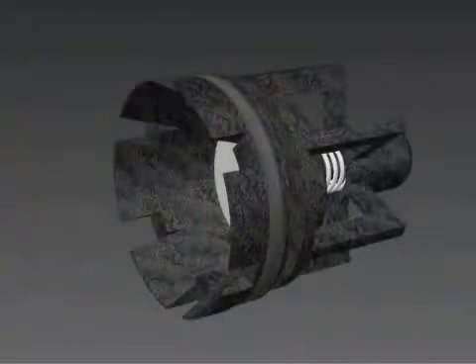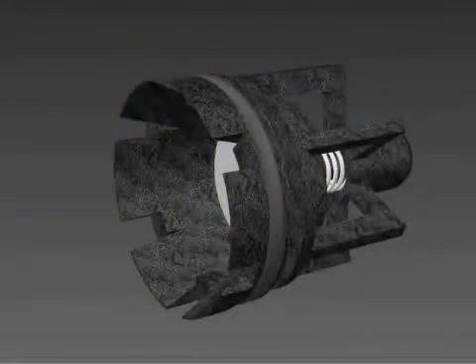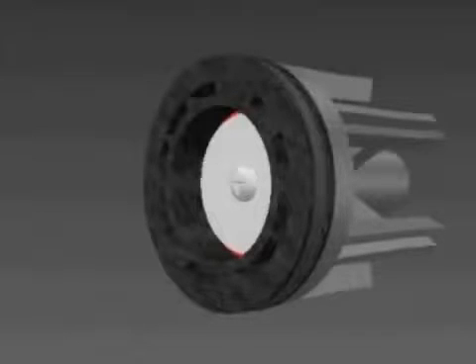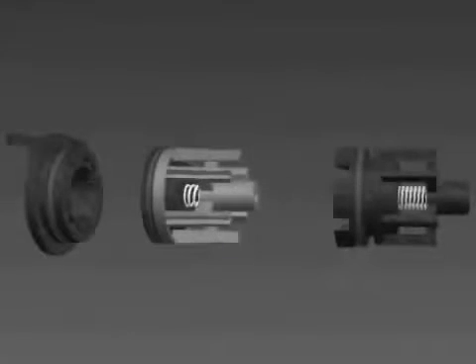Repeat this process with the second check assembly. Make sure to put the stronger spring in the number 1 check assembly. Now you will place your new O-rings on the seats of each check assembly and the sleeve if needed, and lubricate these O-rings.